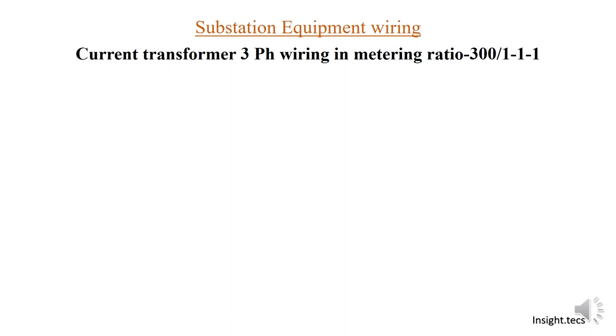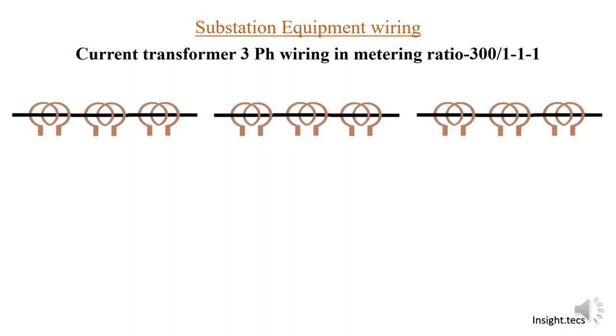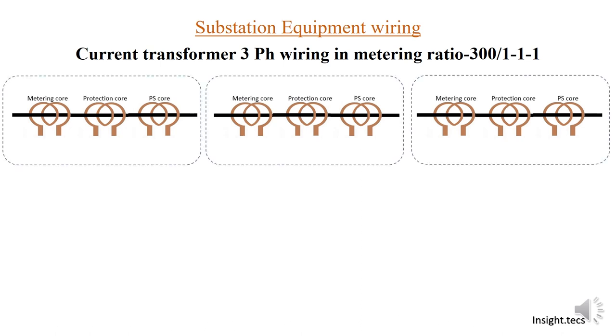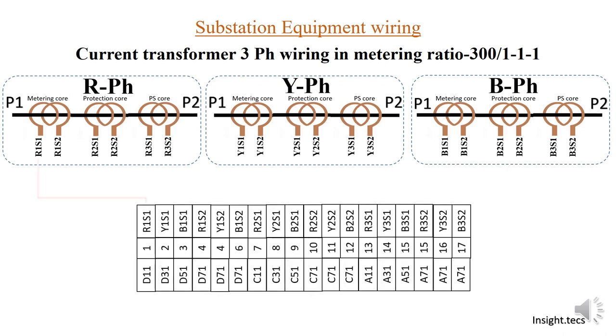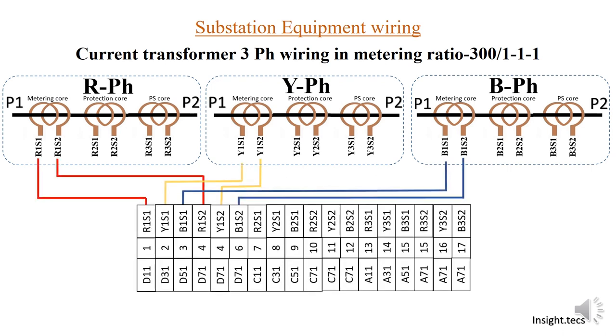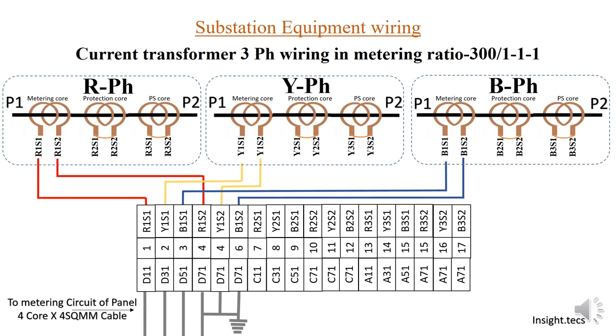Here there is a metering core. As we have seen in the previous videos, what is the metering core? So here there is a 3-phase metering core, and here there are 4 wires: D11, D31, D51, and D71, which go to the control room. Now we will see what the wiring is in the control room.